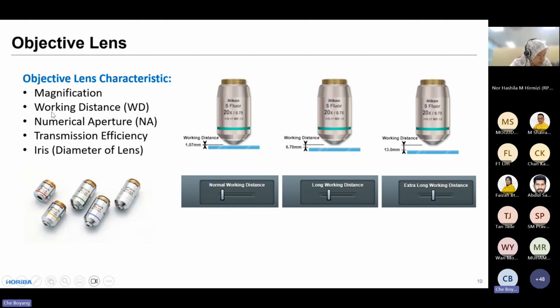Another parameter is called working distance. It's the distance between your objective lens and your sample surface. Each objective lens has a fixed working distance, so you have to find the correct working distance when you are trying to test your sample. Usually for a low magnification objective lens, you will have a relatively longer working distance. However, for a higher magnification, for example a 100x objective lens, you will have a very small working distance.